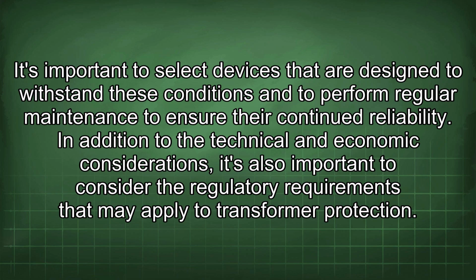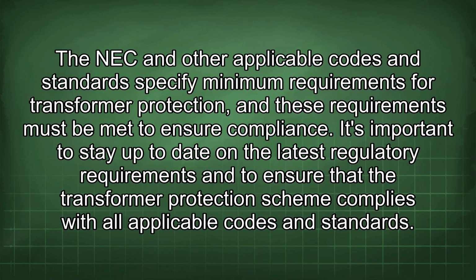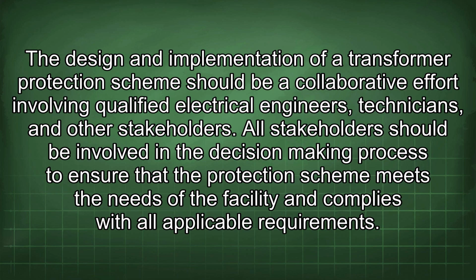In addition to the technical and economic considerations, it's also important to consider the regulatory requirements that may apply to transformer protection. The NEC and other applicable codes and standards specify minimum requirements for transformer protection, and these requirements must be met to ensure compliance. It's important to stay up to date on the latest regulatory requirements and to ensure that the transformer protection scheme complies with all applicable codes and standards. The design and implementation of a transformer protection scheme should be a collaborative effort involving qualified electrical engineers, technicians, and other stakeholders. All stakeholders should be involved in the decision-making process to ensure that the protection scheme meets the needs of the facility and complies with all applicable requirements.